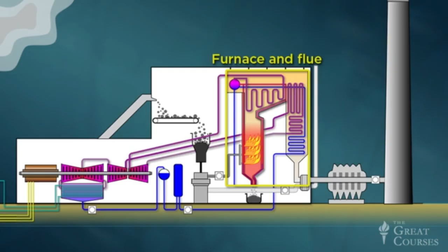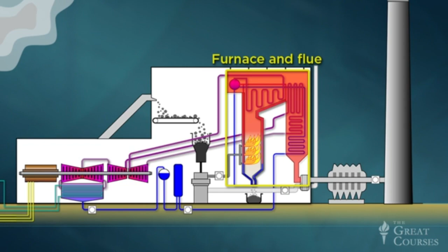The furnace is a huge steel box, about 50 feet square and 130 feet tall. Inside, a 3,000-degree fireball burns continuously, sending a stream of hot exhaust gases up into this arch-shaped flue. As we'll see, the purpose of the flue and its associated equipment is to extract every possible joule of heat from the exhaust gases before they're released into the atmosphere.